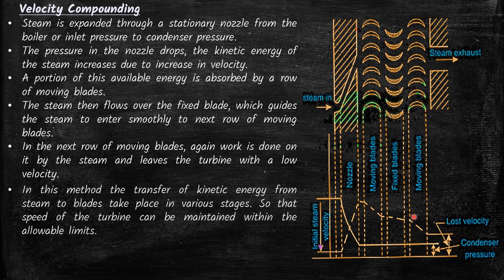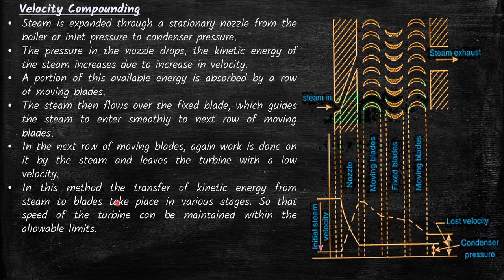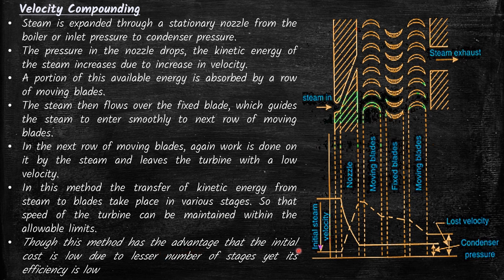In this method, the transfer of kinetic energy from steam to blades takes place in various stages, so that the speed of the turbine can be maintained within the allowable limits. We are transferring the kinetic energy from the steam to the turbine in stages — first in the first row of moving blades, then in the second set of moving blades. Though this method has the advantage of low initial cost due to fewer stages, its efficiency is less compared to other compounding methods.